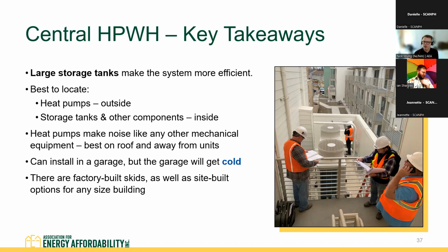Next question: do you recommend water softeners to extend the life of a central heat pump water heater and the associated plumbing runs? It really depends on the water quality in your particular area. You should talk to the heat pump manufacturer, and make sure your engineer is looking at the water quality reports for the location where you're building. All of this equipment will have requirements and recommendations around water quality, so it's about making sure you're operating within those parameters. It's going to be different for every location.